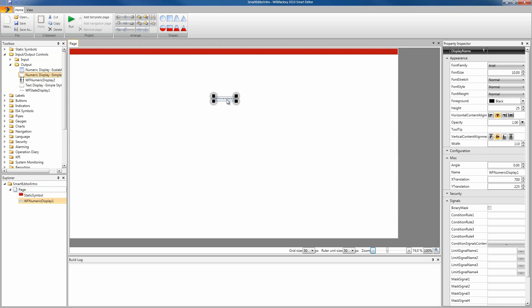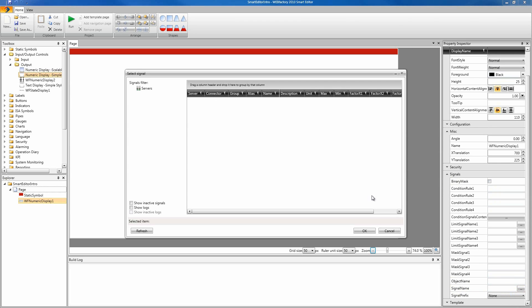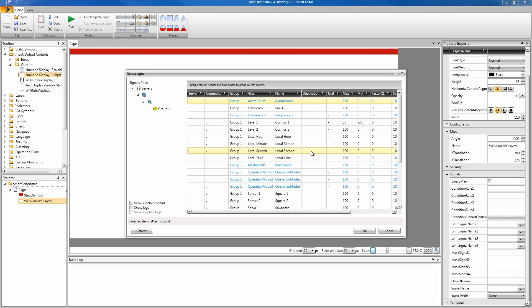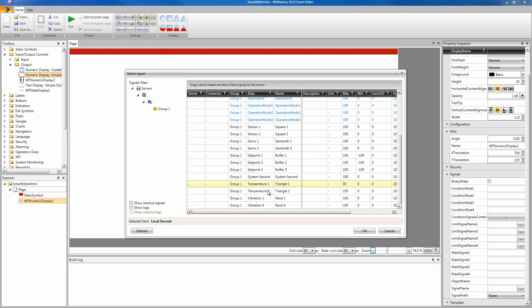If we select this numeric display, we can go into the signals tab of the property inspector and we can select and attach a signal. Go into the signal name property, click on the browse button and let's select a signal from our server. First of all, you gotta make sure that the demo project is running in the Web Factory Studio and that you have the Web Factory Server started. I'm gonna select the signal set point 2, for example.